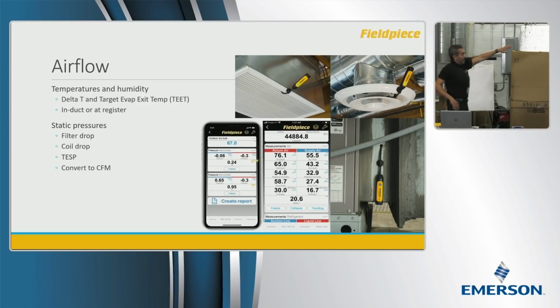So going back to airflow, these measurements are very simple and don't take a lot of time to do, but they deliver a lot of information and understanding of how the airflow is working. When it comes to system troubleshooting, we want to be able to take good measurements fast. We don't want to spend a lot of time trying to find the problem. However we can do it faster, better, and more accurately is going to help you do your jobs better, have a happy customer, and generate more revenue. And finally, you can also convert static pressure readings into CFM by looking at a manufacturer fan table and finding your CFM value, if you need to do so.